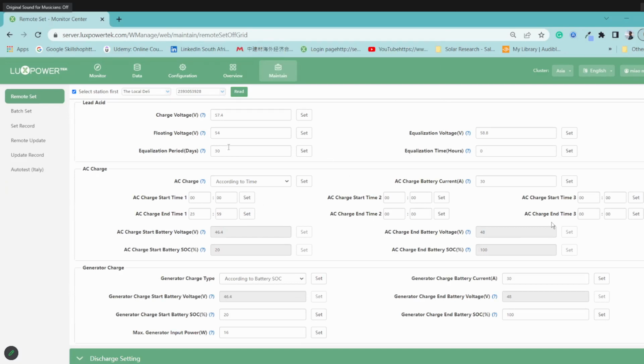Setting up the AC first, you've got 3 time slots over here. So you can try and program it and tailor it based on what the client wants. I believe this is quite useful in some situations where the power coming from the grid is not very stable and not reliable. So you guys can schedule this, including with AC first. So if you have to select AC voltage or AC charge according to battery voltage or SoC, it will highlight the appropriate section of here, and then you can just program it over there.